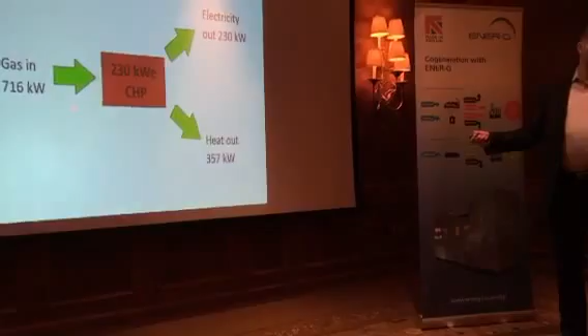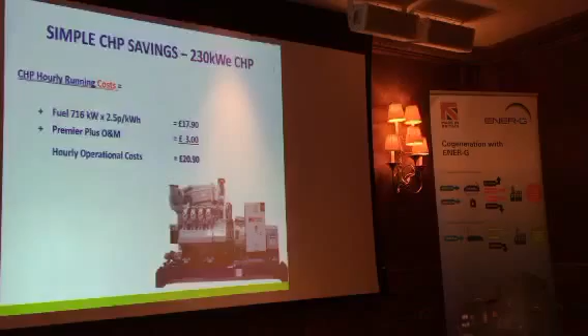Typical balance for a machine like the one downstairs: a 230 kilowatt electrical output, giving 357 kilowatts of heat, with 716 kilowatts of gas going in. So how much is that costing us to run? Taking it over one hour at full load, it's costing us £17.90 in fuel to run for one hour. Doesn't sound like a lot, and you can see the gas price is 2.5p a kilowatt hour.